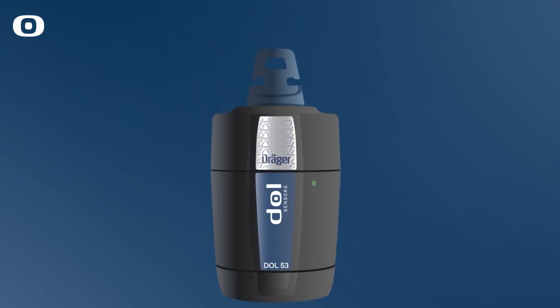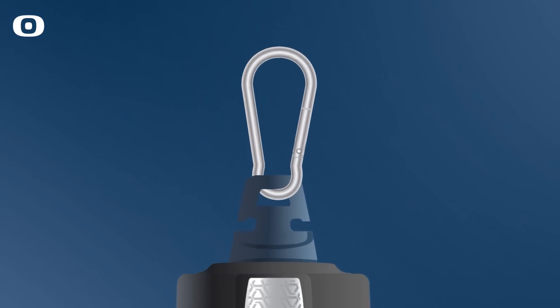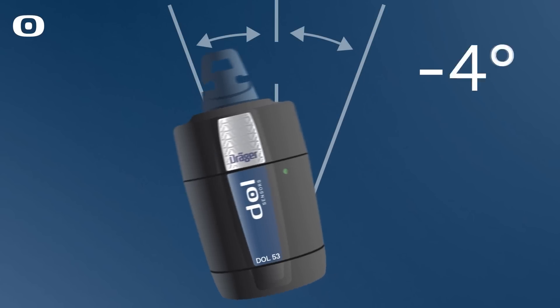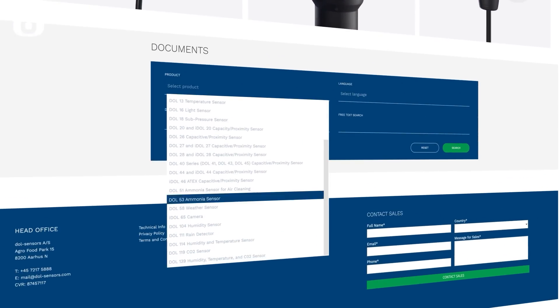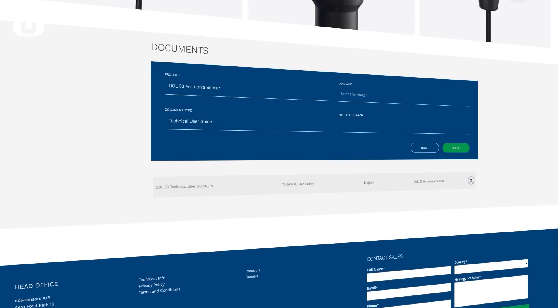Mount the sensor in the mounting lug at the top of the sensor, filter facing down. The offset from the vertical must be max 15 degrees. Please follow all of the instructions in the technical user guide, which is found on www.dol-sensors.com.